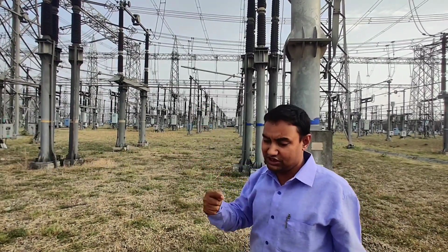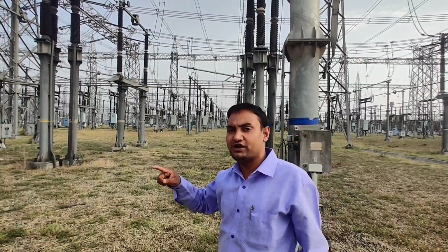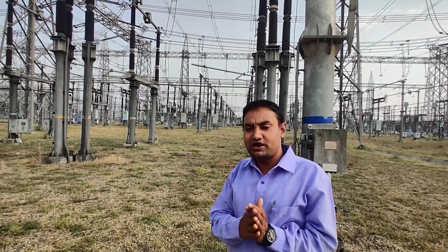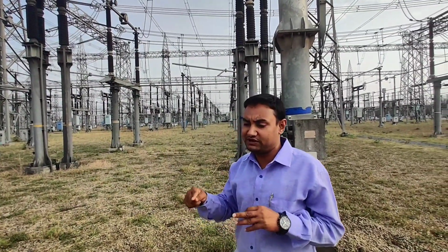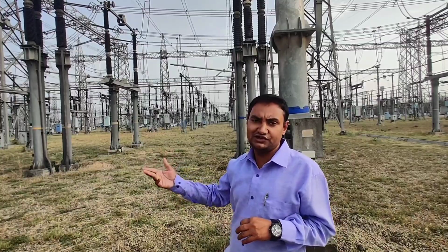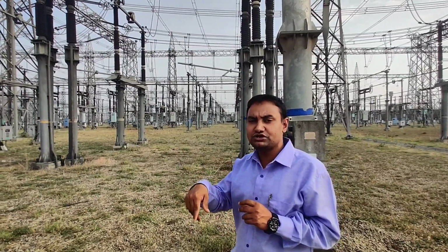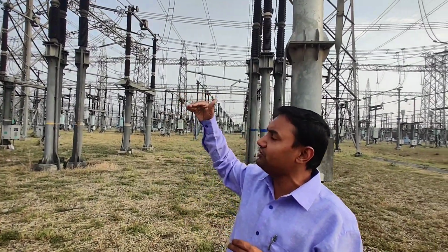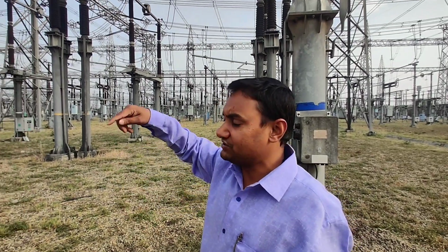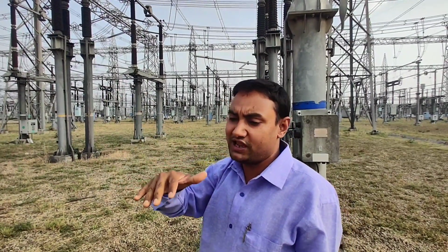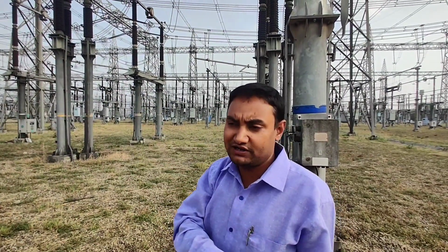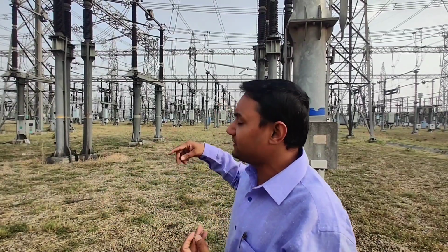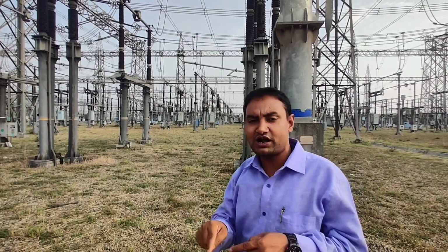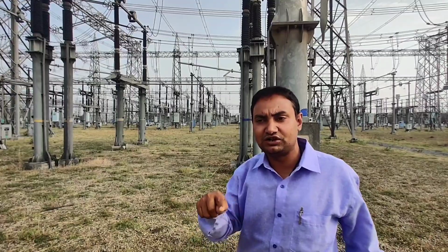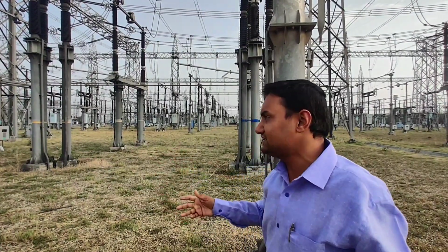Now if you are reducing that 400 kV to 110 volt directly using only a potential transformer, then the size of that transformer will be very large. That's why we are not using potential transformers nowadays. What we are doing is, through a set of capacitors, we are reducing that 400 kV voltage to a certain voltage level, suppose 33 kV, and after that we are using a smaller transformer for reducing that 33 kV to 110 volt in the secondary.